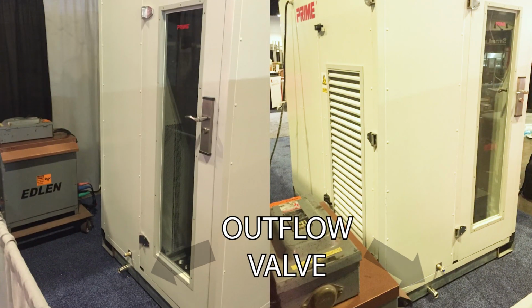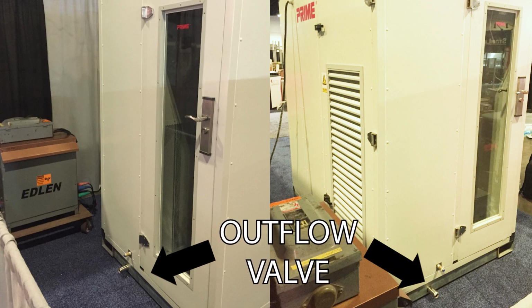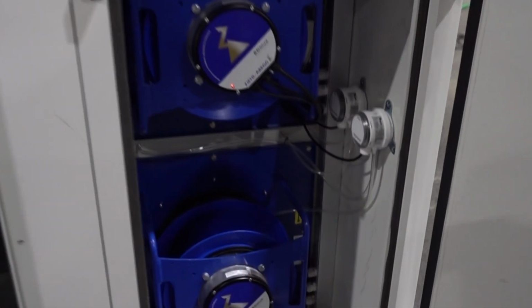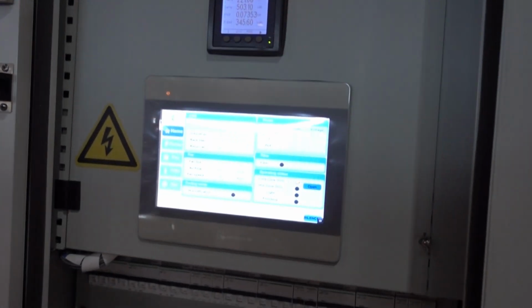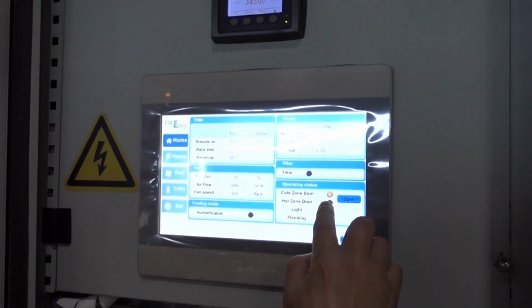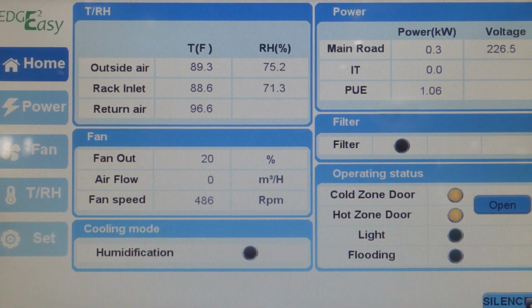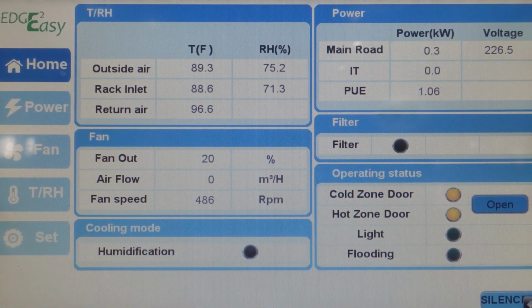This moisture evaporates as it's being drawn through the super efficient fans to provide exactly the right balance of humidity. Any water that doesn't evaporate exits the MDC through the outflow valve beneath the water connector. These powerful German-built fans push the air into the cold aisle along with the right blend of evaporating moisture when needed. The brain behind how our MDCs work so efficiently is the Siemens Environmental Programmable Logic Control System that can be operated on-site or remotely.